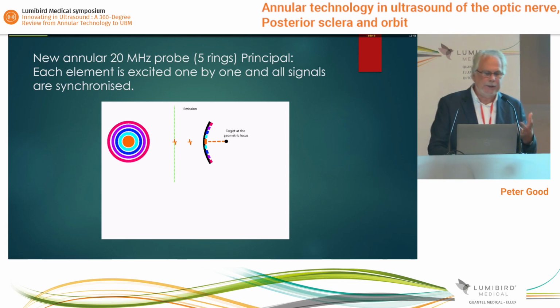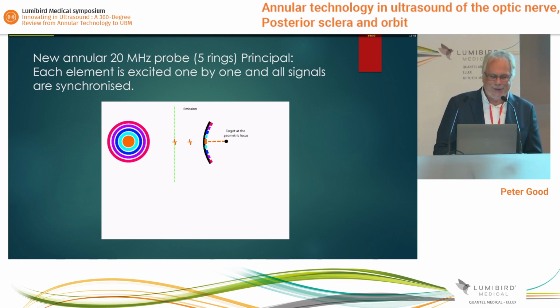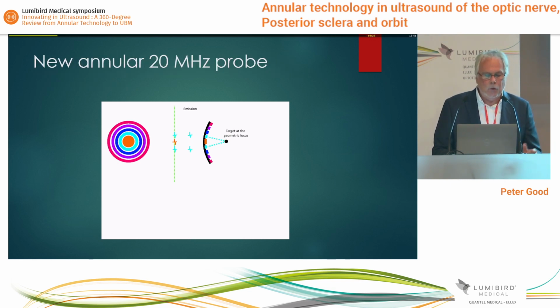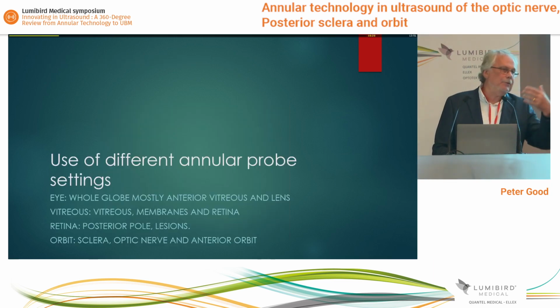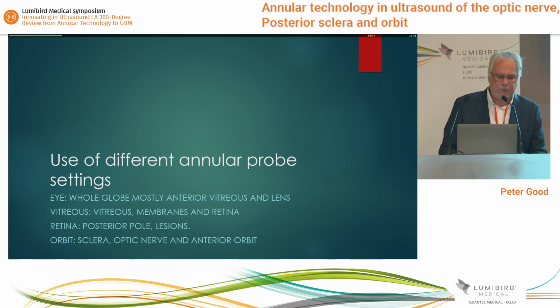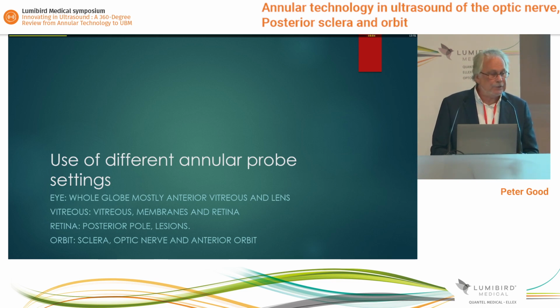So how does it basically work? Well, you have 5 annular transducers within the probe, and when you fire up different transducers, fire up is a very bad term, but that's the only one I can think of, you basically will look at different parts of the globe. So the more 4 and 5, you start to get towards the orbit. The orbit, in fact, is a feature seen on a 15 megahertz probe, but the main ones we use are eye, vitreous, and retina. So eye is basically the first 2 transducers, then vitreous 3, and then 4 and 5 looks at the retina and orbit.